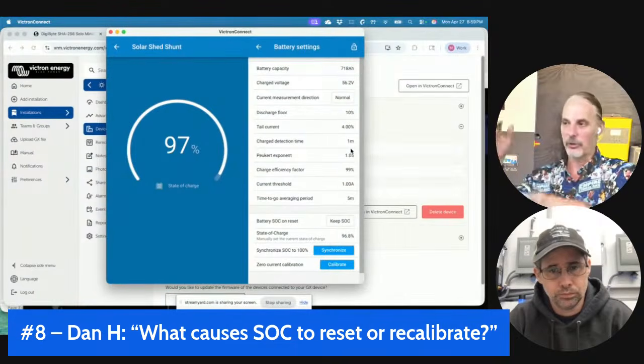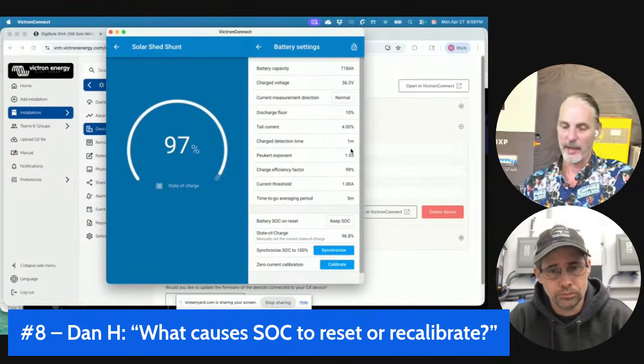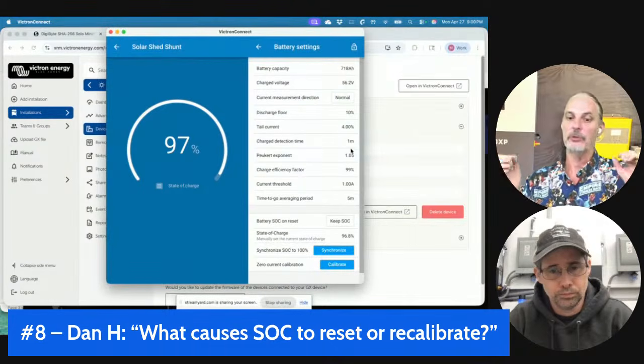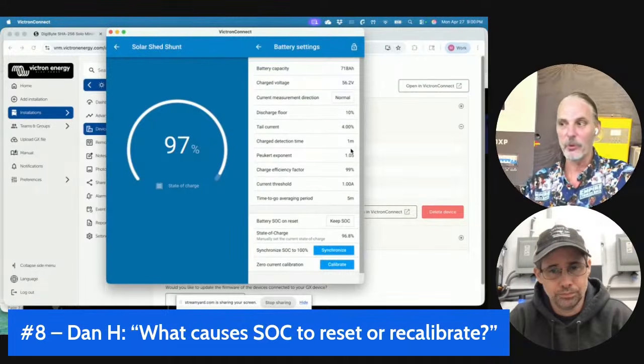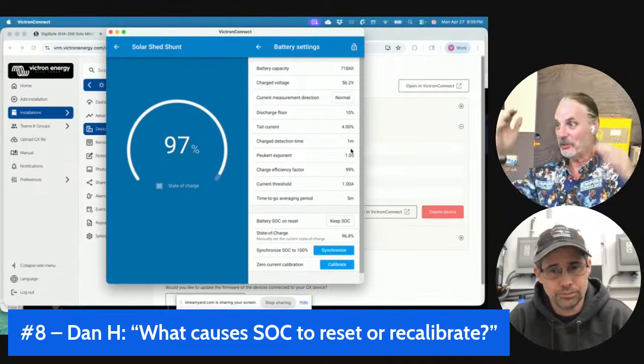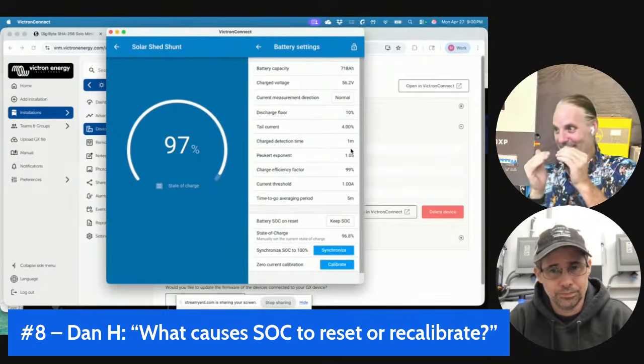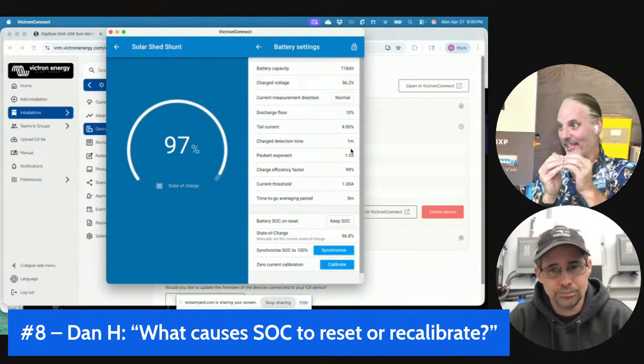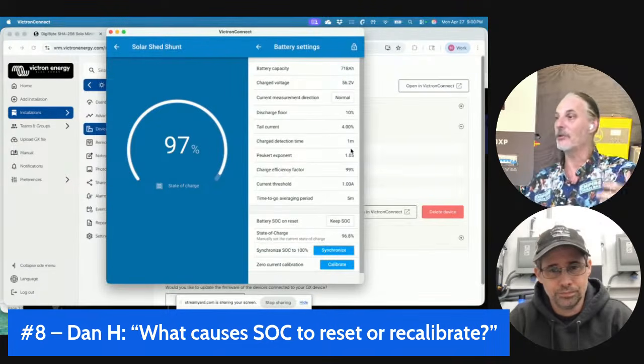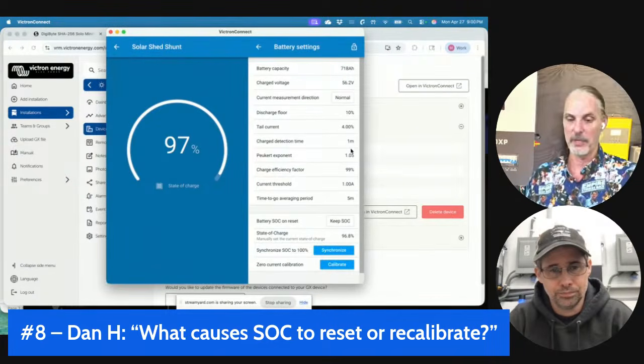Now in the charge controller you could actually set absorption time and all that. But here with just a shunt, you can say, hey, I want you to drop below 1 amp and maintain it for 5 minutes. The reason it's important to set that time is because you can temporarily have all your loads drop to where everything comes in at half an amp for 10 or 15 seconds, and it looks like it's at a full charge. So you have to set it so it consistently holds for 1 minute.